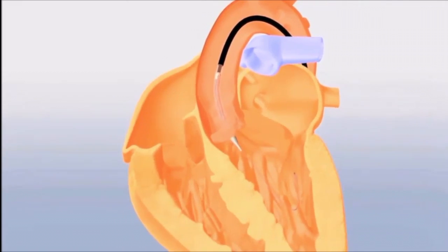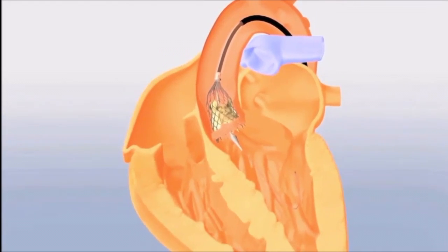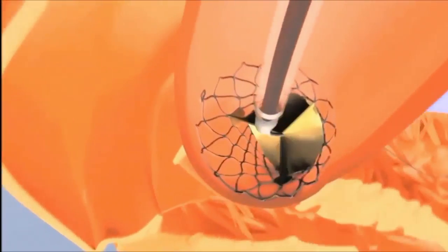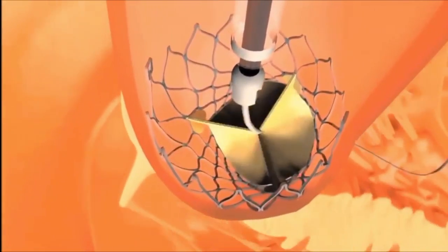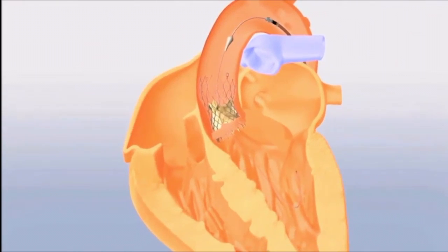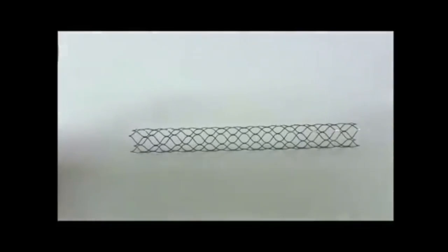Once in place, the CoreValve system's self-expanding frame enables physicians to deploy it in a controlled manner, allowing for accurate placement. Here the device expands and takes over the original valve's function to ensure that oxygen-rich blood flows efficiently out of the heart and circulates throughout the rest of the body. The catheter is then removed from the patient's body and the incision in the...